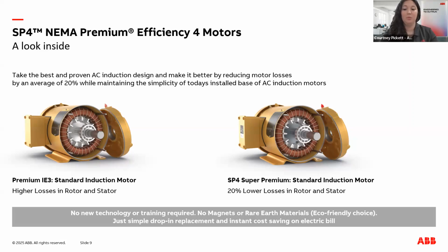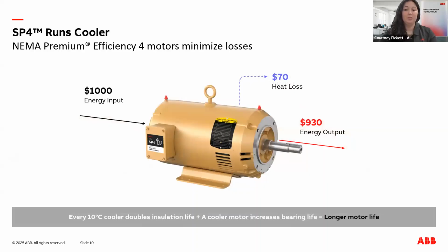One of the biggest ways that SP4 motors deliver those savings is through heat reduction. One of the biggest performance killers in motors is heat. Inefficient motors don't just waste energy, they convert it into heat, which shortens your insulation life, wears down your bearings, and can increase your failure risk. In this example, you'll see a motor with 93% efficiency, which means that about $70 of every $1,000 in energy is lost as heat. The SP4 motor runs cooler, meaning lower internal temperatures, longer lifespan, and fewer unexpected shutdowns. With every 10 degrees Celsius drop in temperature, you typically double the insulation life. So with that, we stand behind these motors with a 4-year warranty.